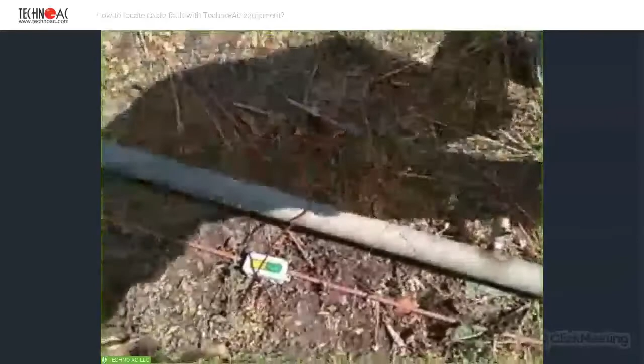Of course, in a normal situation we would have to dig the cable out, but this is our demo cable, and it's not a surprise that the cable damage will be here, because our current is leaking from the cable to the ground. That is why we can detect this. So yes, it's approximately 20 meters from our connection point, the cable which is on the barrel. But let us switch the conductors of the cable.